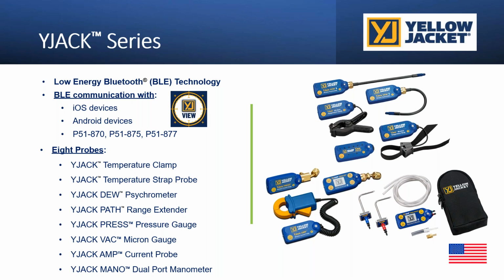Unique to our pressure probes is that we actually have an access port on them, so a contractor can charge through our pressure probes. A lot of competing pressure probes out there don't have that access port, so all a contractor can really do is diagnose a piece of equipment. If they wanted to top it off with refrigerant, they'd have to get their manifold out of the truck and hook it up. With ours, you can literally take your hose, attach it to our pressure probe, and weigh that refrigerant directly into the system.